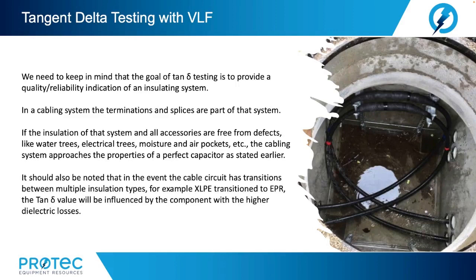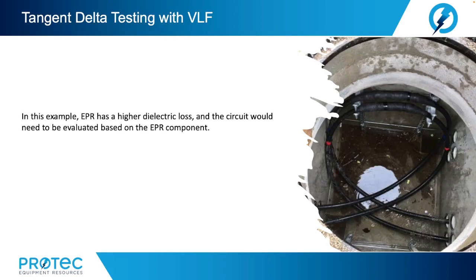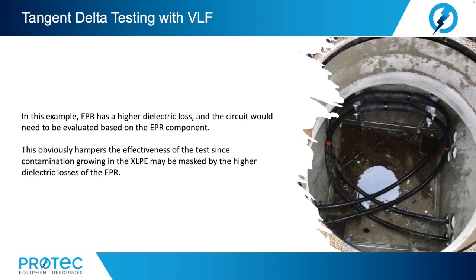It should also be noted that in the event the cable circuit has transitions between multiple insulation types, for example, a cross-link polyethylene cable transitions into an ethylene propylene rubber or EPR, the tan delta value will be influenced by the component with the higher dielectric losses. Now, in this example, ethylene propylene rubber, or EPR, has much higher dielectric losses than the cross-link polyethylene portion of the circuit, and the tan delta results will be influenced by the EPR component. This obviously hampers the effectiveness of the test, since contamination growing in the cross-link polyethylene portion of the cabling system may be masked by the higher dielectric losses of the ethylene propylene rubber.